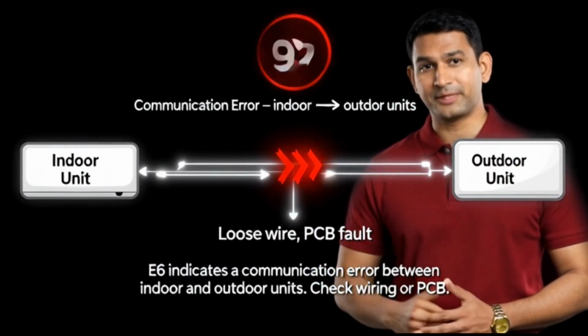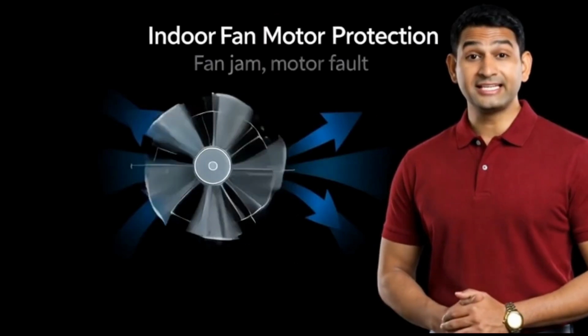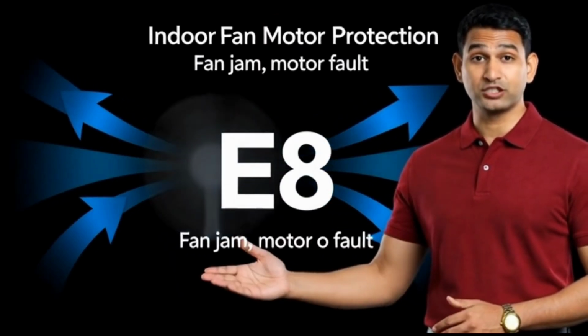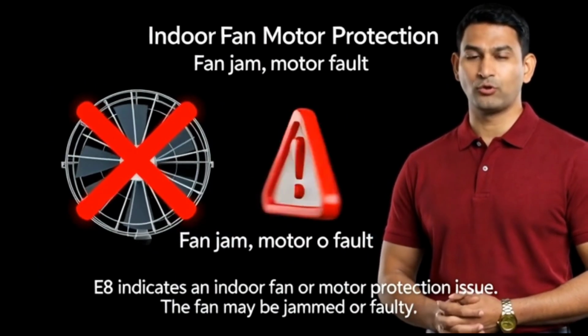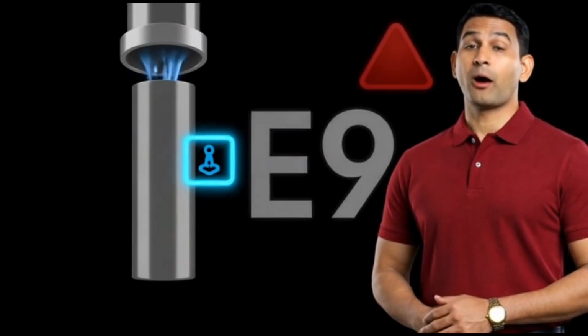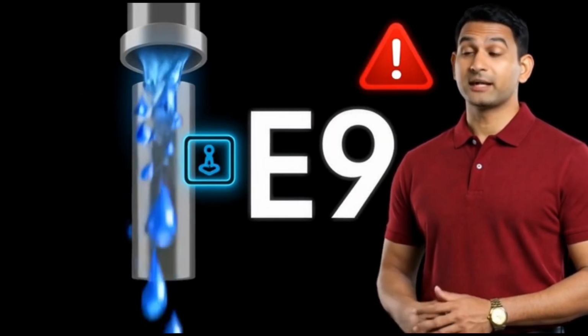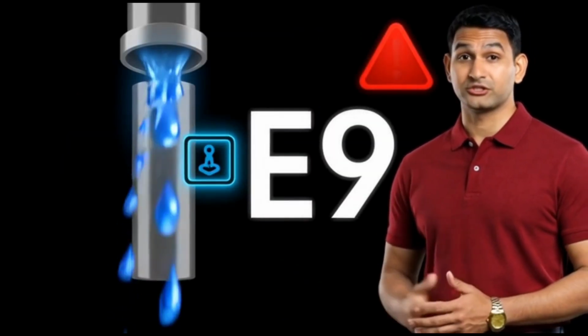Check wiring or PCB. E8 indicates an indoor fan or motor protection issue. The fan may be jammed or faulty. E9 indicates a problem with water flow or the drain line. This could be caused by a blocked pipe or a sensor issue.